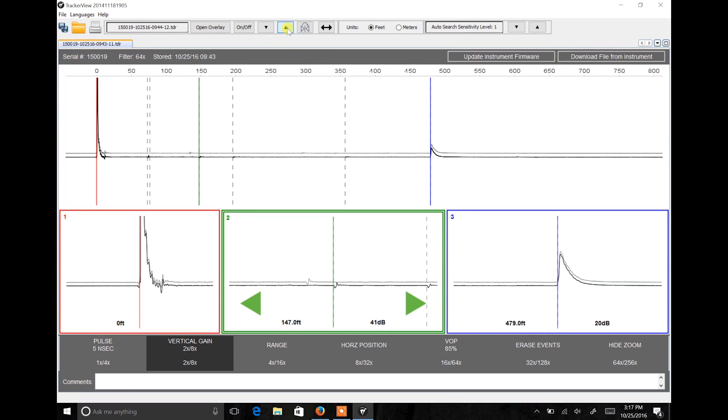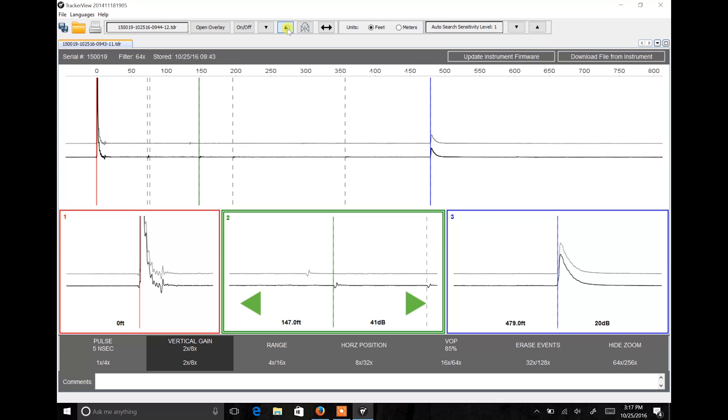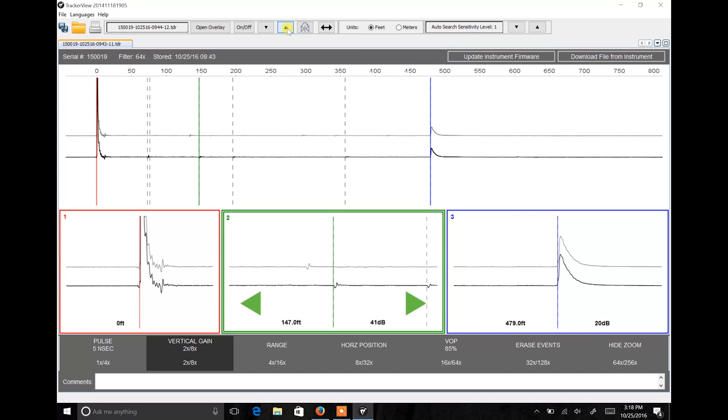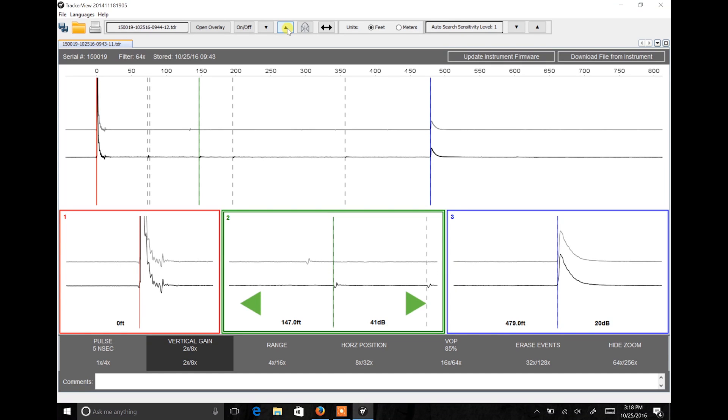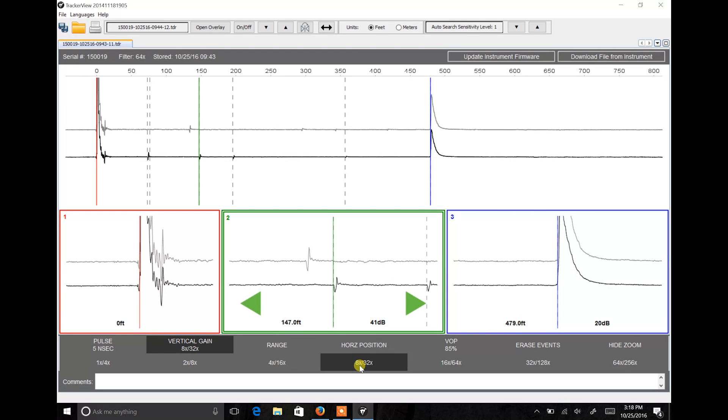Once Tracker View has the file open, you can use the arrows to move the overlay up or down so that you can see both files at the same time. The vertical gain control increases or decreases the vertical amplitude or gain of the waveform display. Increasing the vertical gain allows the user to see smaller reflections or minor faults on the cable signature.